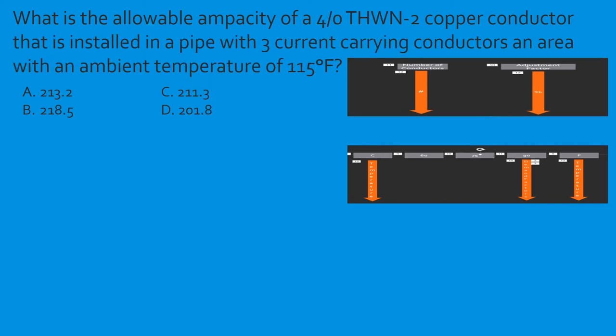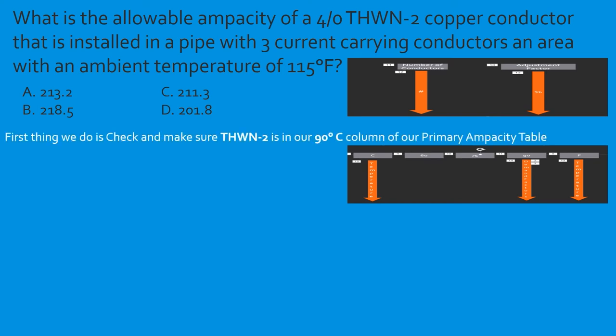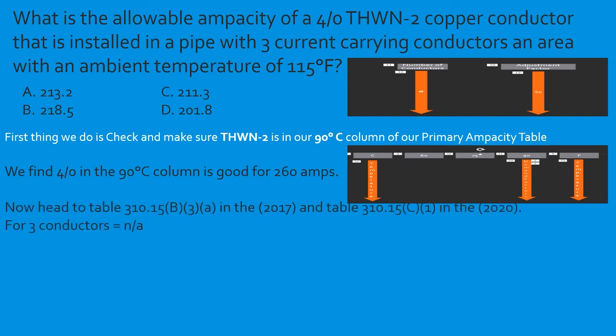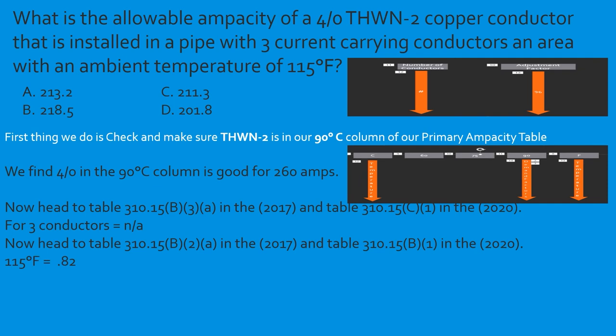Question: What is the allowable ampacity of a 4/0 THWN-2 copper conductor installed in a pipe with three current-carrying conductors in an area with an ambient temperature of 115°F? Confirm insulation is in the 90°C column. 4/0 THWN-2 in the 90°C column is 260 amps. With only three current-carrying conductors, the bundling adjustment does not apply — it only applies for more than three. Correction factor at 115°F is 0.82. So: 260 × 0.82 = 213.2 amps. Select A.